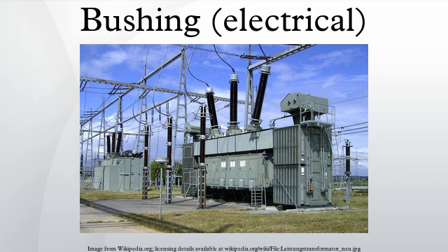Resin insulation. Since the 1960s, resin materials have been used for all types of bushing up to the highest voltages. The flexibility of using a castable form of insulation has replaced paper insulation in many product areas and dominates the existing insulated bushing market. As with paper insulation, the control of electric stress fields remains important. Resin insulation has greater dielectric strength than paper and requires less stress control at voltages below 25 kV.